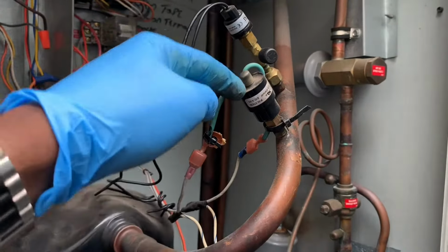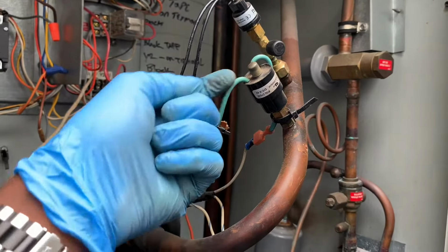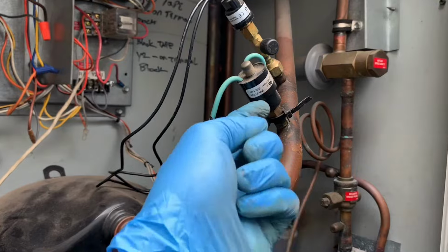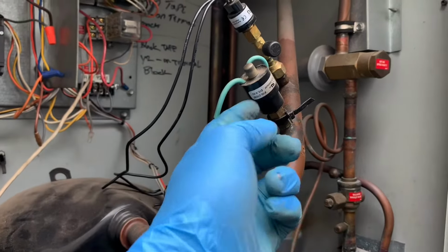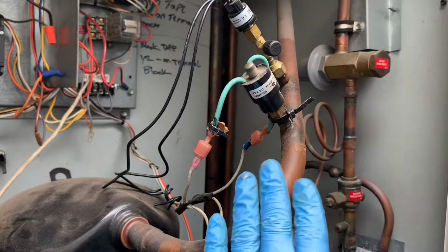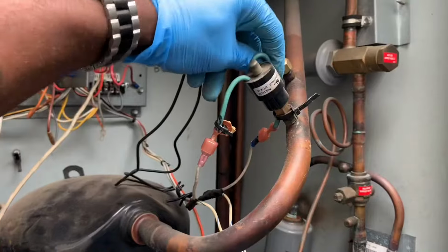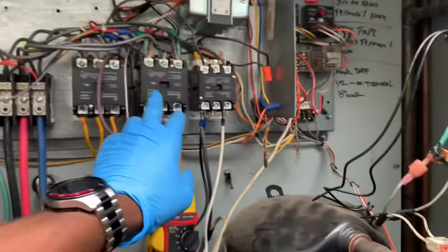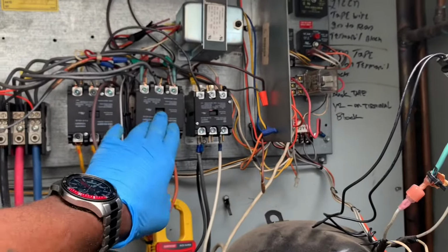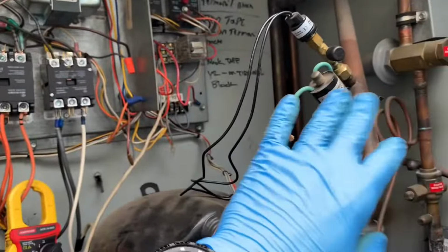It's just 1 wire in, 1 wire out, and electricity is flowing through here, going through the contacts, the switch inside here, hence the term high pressure switch or low pressure switch. The switch inside is always closed once everything is okay with the pressures in the system, and then electricity flows through, comes back out the other side, and continues on down the circuit. It's a part of the circuit that controls the compressor contactor, and if the safety is good, it remains closed, and the compressor runs.